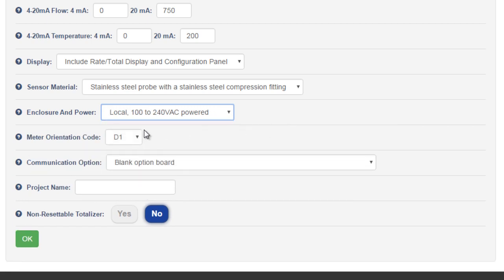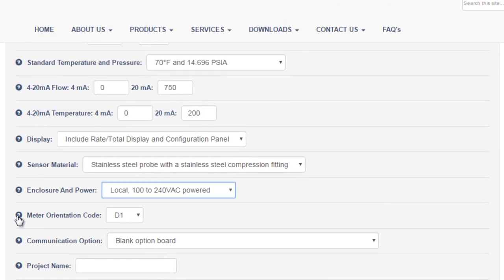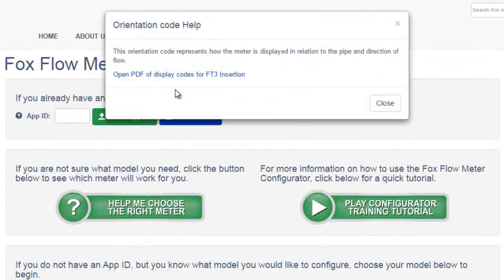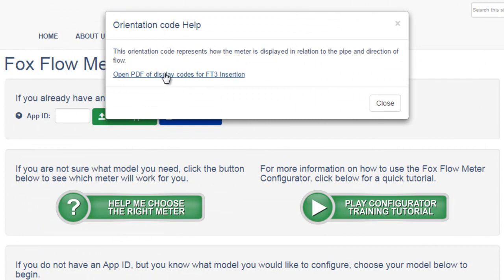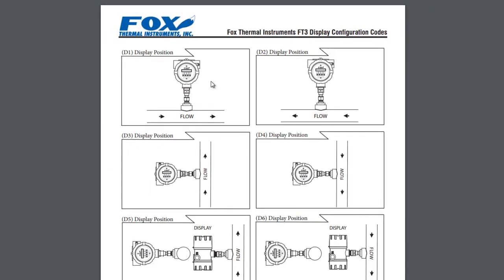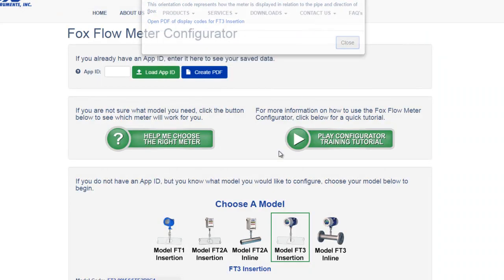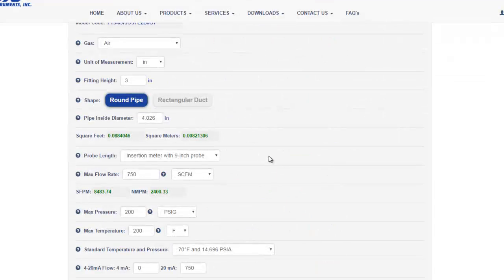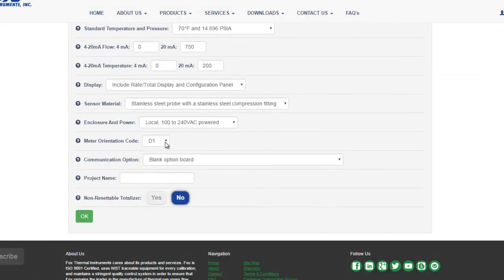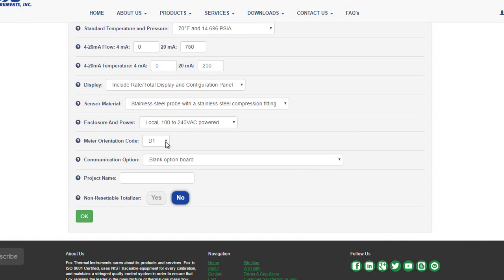With the local display on an FT2A or an FT3, you must choose how your display is going to be oriented around the pipe. To see the available options, click the help icon. You'll see this pop up with a link to the FT3 insertion display codes. We'll take a quick look here. You'll see the flow meter oriented around the pipe in many different ways depending upon the direction of the pipe, horizontal or vertical, and the direction of flow. But let's go back to the configurator. We'll stick with the D1 orientation code for horizontal pipe with flow from left to right.